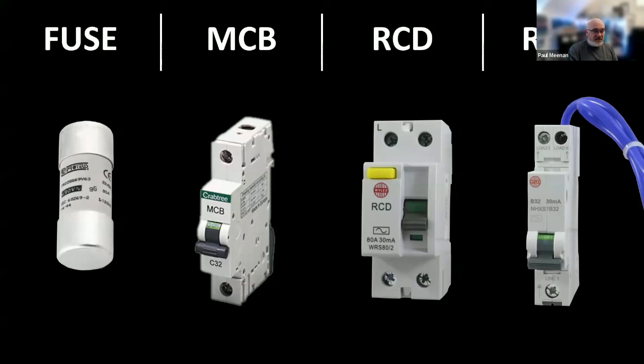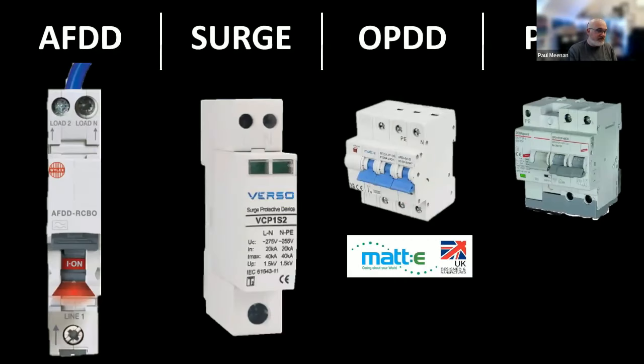We've obviously been on a journey: BS 4293 standard RCDs, which we would use two of in a board to split the installation in half, and that would look for earth leakage up to 30 milliamps. Thankfully, we have technology, and the wonders of technology allowed compact RCBOs, which have a little neutral reference lead. That's standard in most installations now, probably in the last 5 to 10 years in the UK, and that's a type A as well. Interestingly, some of them have additional leads, functional earths, because some may rely on a connection to earth so that they can operate and function correctly, to get an earth reference.